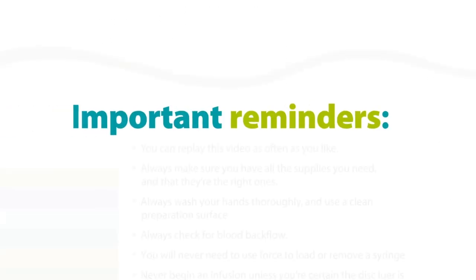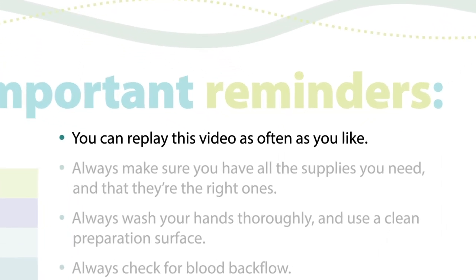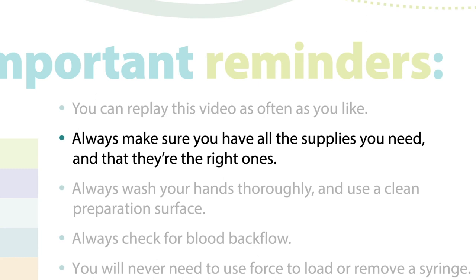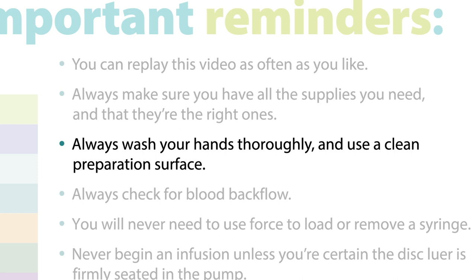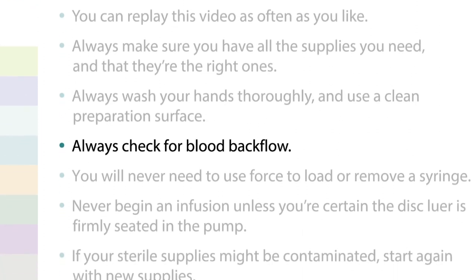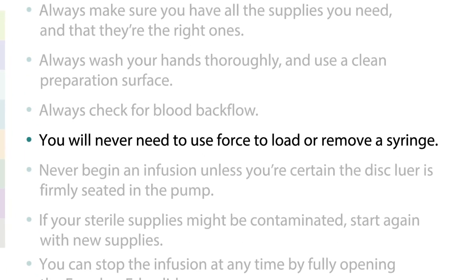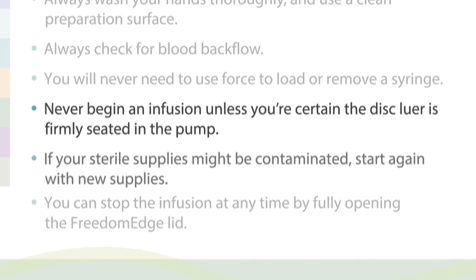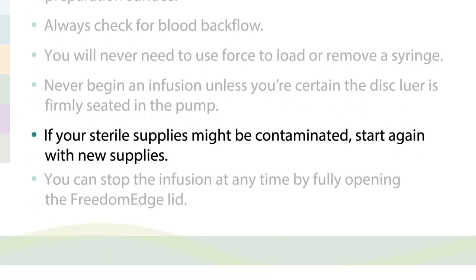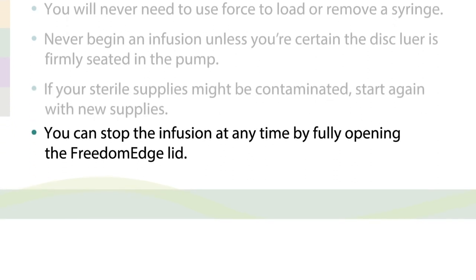Important Reminders: You can replay this video as often as you like. Always make sure you have all the supplies you need and that they're the right ones. Always wash your hands thoroughly and use a clean preparation surface. Always check for blood backflow. You will never need to use force to load or remove a syringe. Never begin an infusion unless you're certain the disc luer is firmly seated in the pump. If your sterile supplies might be contaminated, start again with new supplies. You can stop the infusion at any time by fully opening the Freedom Edge lid.